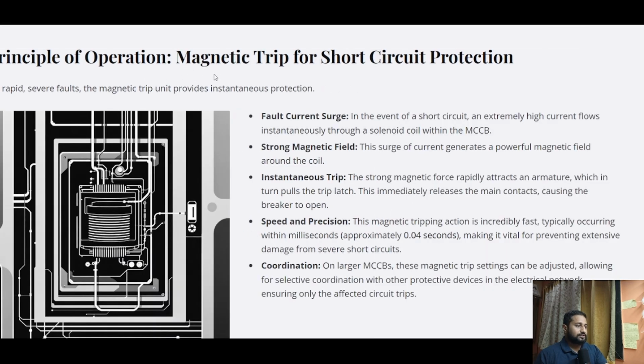Then the next principle of operation is magnetic trip for short circuit protection. So, fault current surge. In the event of a short circuit, an extremely high current flows instantly through the solenoid coil within the MCCB. Then it gives a strong magnetic field. This surge of current generates a powerful magnetic field around the coil. The strong magnetic force rapidly attracts an armature, which in turn pulls the trip latch. This immediately releases the main contacts, causing the breaker to open.